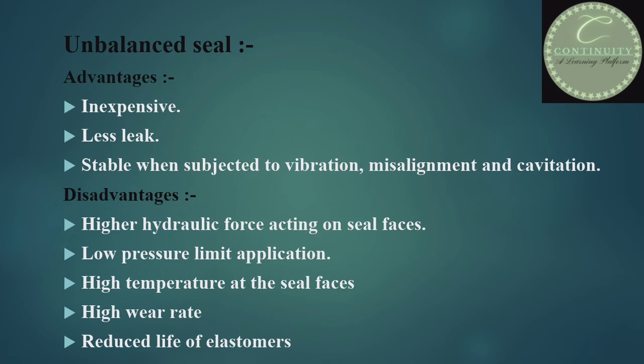Advantages and disadvantages of the unbalanced seal. Its advantages are that it is inexpensive and has less leakage compared to balanced seal. It is stable when subjected to vibration, misalignment, and cavitation. Disadvantages: higher hydraulic force acts on seal faces. It is used for low pressure applications only. High temperature is generated at the seal faces due to high wear, and high wear rate also reduces the life of elastomers.